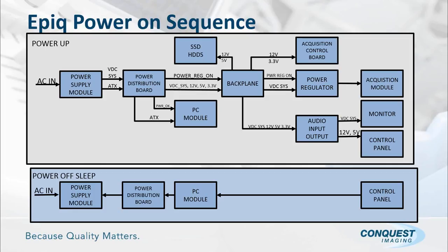Moving to the next slide, this is what happens then. Now the power supply module has been told to power on. It now generates the system DC voltage, the 24 volts, as well as the ATX voltage. Let's talk about the ATX voltage first. The ATX simply goes through the power distribution board and into the PC module, where it receives the power supply okay signal, saying that I'm in my range, 21 to 30 volts. And when it gets that, the PC module is free to power on.